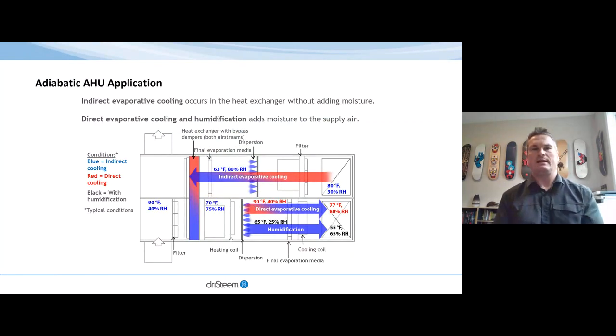So when we look at adiabatic and air handling application, there's direct and indirect evaporative cooling that can be set up or that can happen. Indirect, meaning that we're not going to be introducing that moisture within the space, that the moisture is really being applied more for a heat exchanger and cooling without adding that moisture into the environment. Direct evaporative cooling and humidification means that we would be taking that air, and the air that it's cooling is also going to be the air that it's humidifying, which would be applied directly in that room space.